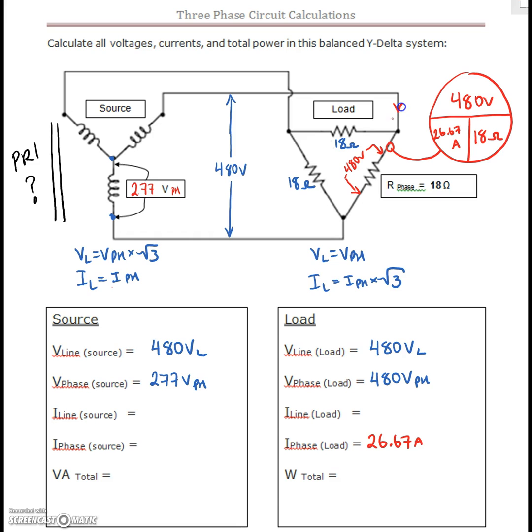When that current comes into the delta, it takes two paths. It doesn't take them at the same time, they go 120 degrees out of phase, but we can see that the current disperses along these two lines here. So this line current on the outside of the delta has got to be greater. For our line current, we're going to take 26.67 amps and multiply that by root 3.